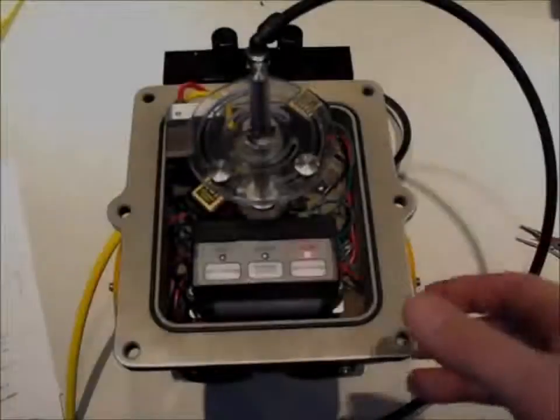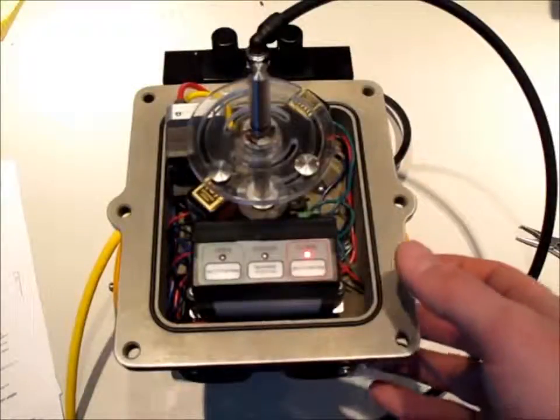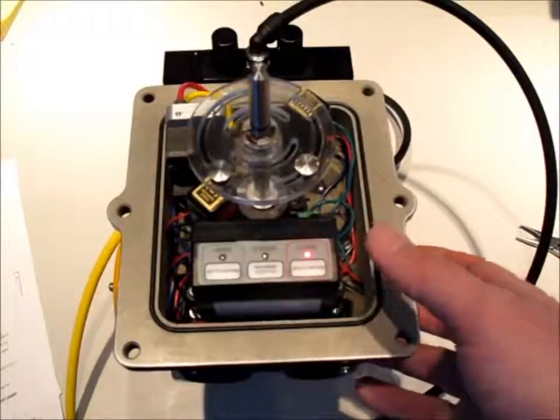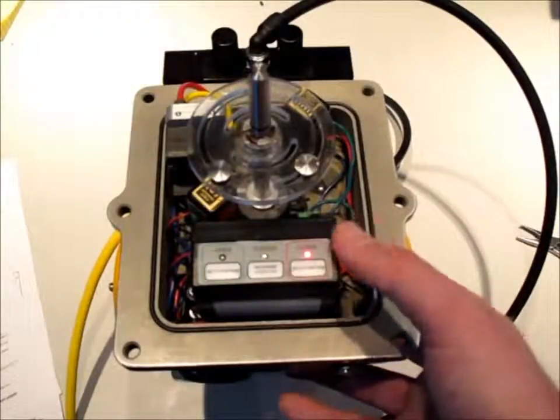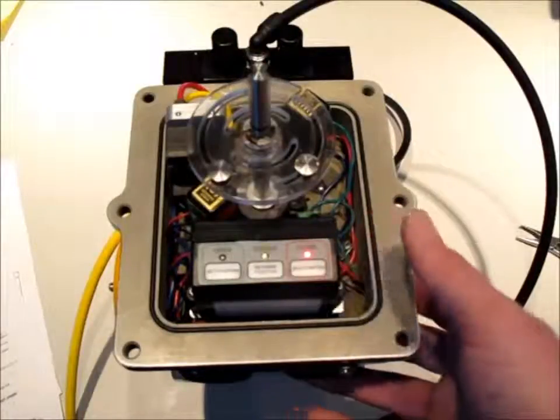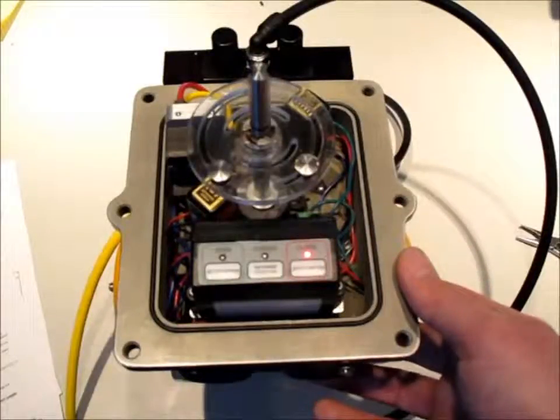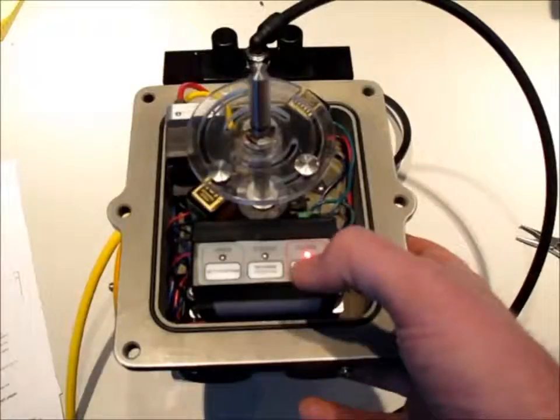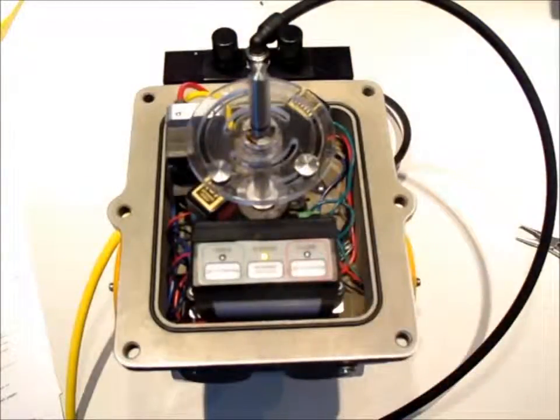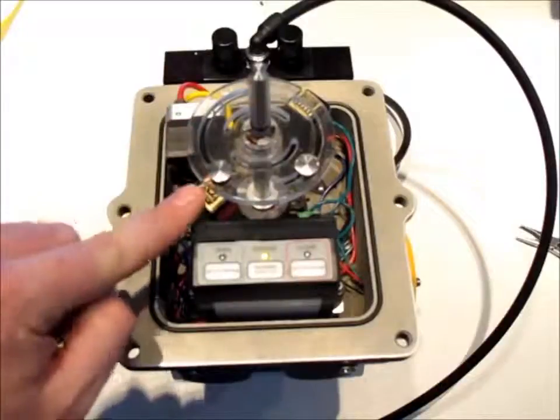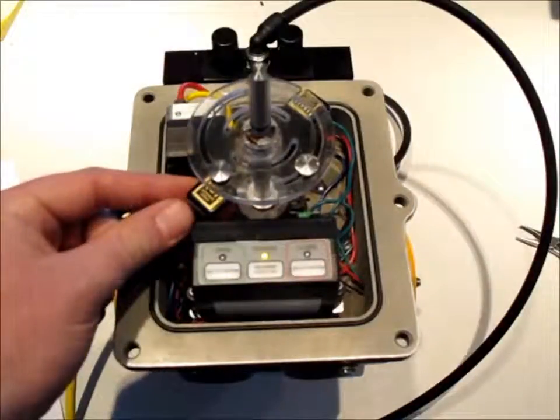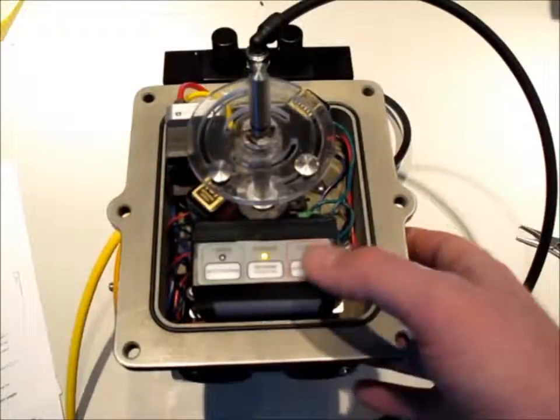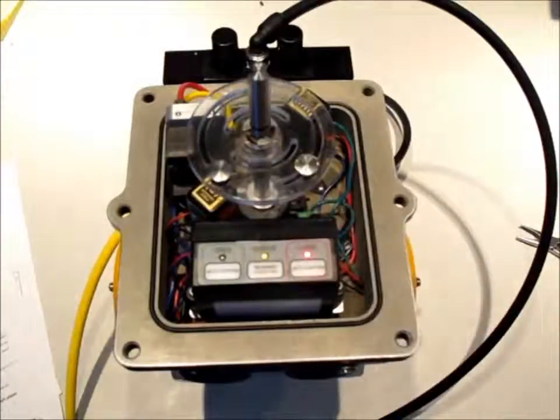To calibrate locally, not over Delta V or with a handheld, move the actuator to the closed position and press the set key. Once you've confirmed that the target magnet is in place and over top of the closed switch, confirm with the same button.